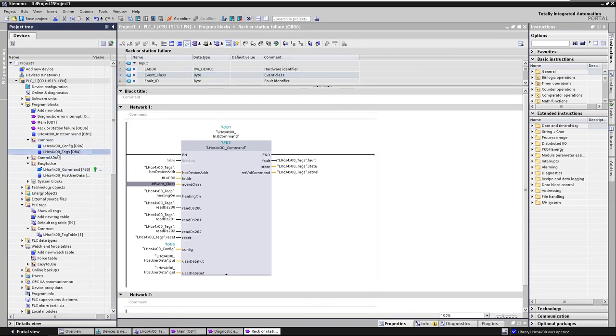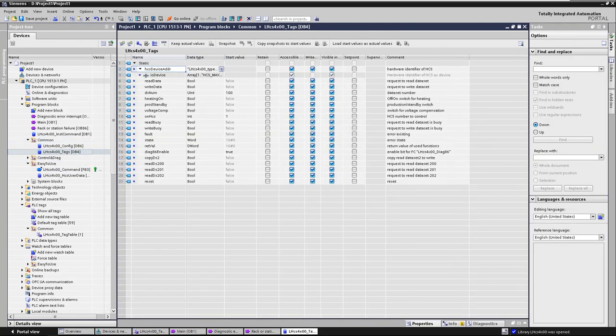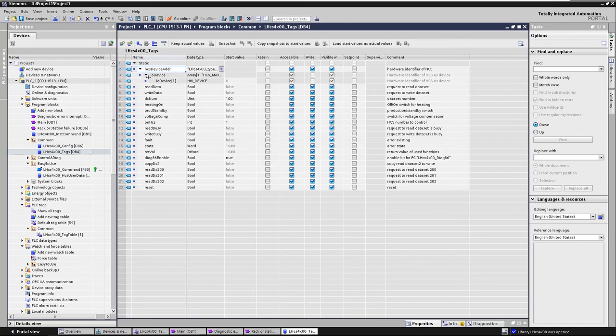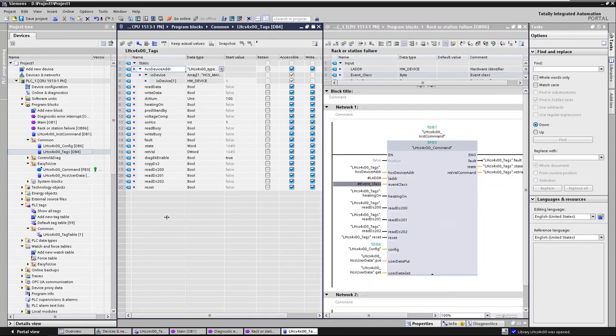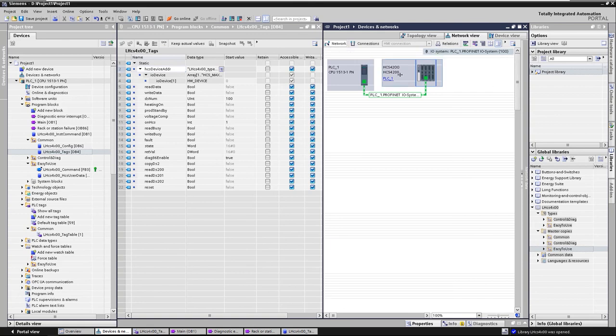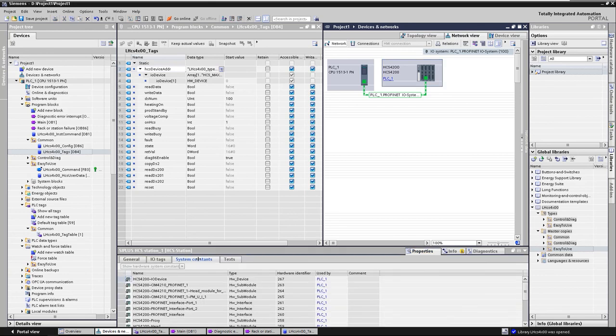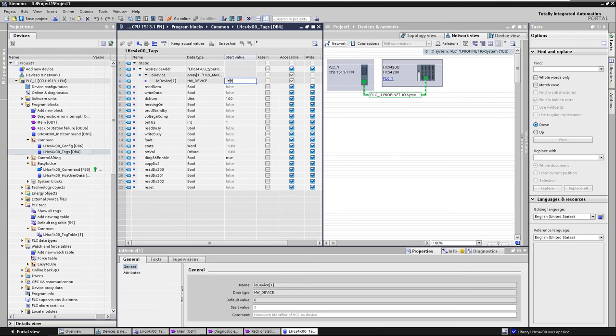To identify the HCS, the hardware ID of the IODevice must be specified in the DB tags. Open the array IODevice under HCSDeviceAddress. Enter here the value that you find in the network view when you select the HCS under Properties System Constants.